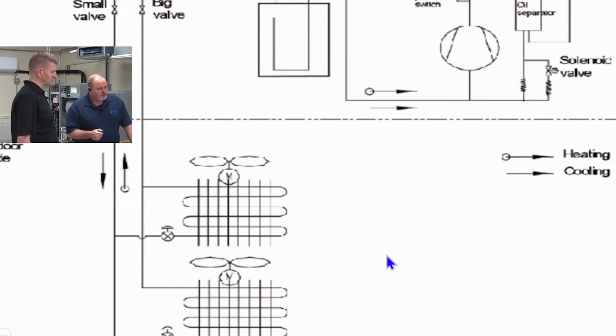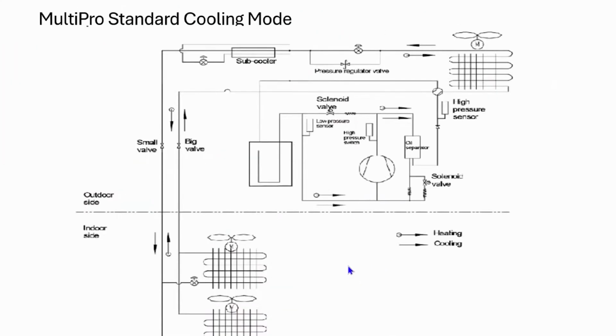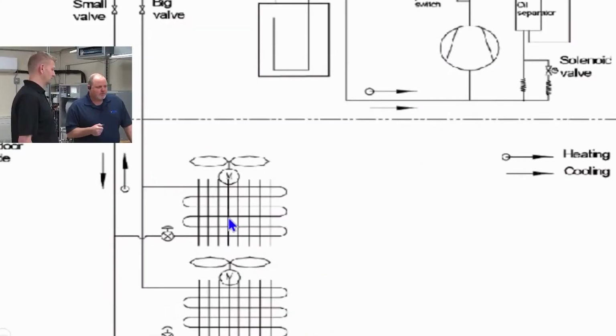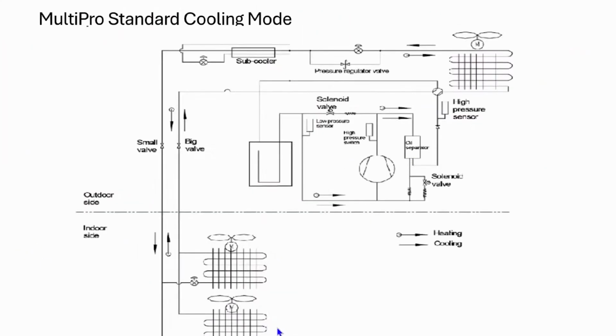And if I have 4 indoor units and the other 3 are working fine, I'm not going to get that compressor error code. But if I shut this one down, shut that one down, shut the other one down, and leave that one on, now there's a good possibility I'm going to get a compressor error code, because the refrigerant's trying to pump up against a block that it can't get through. I'm not getting my cool refrigerant gas back to the compressor. The machine's going, what is going on here? Either a low pressure or high pressure fault, possibly, or even just the amp draw on the compressor went too high because it's beating up against the head pressure.